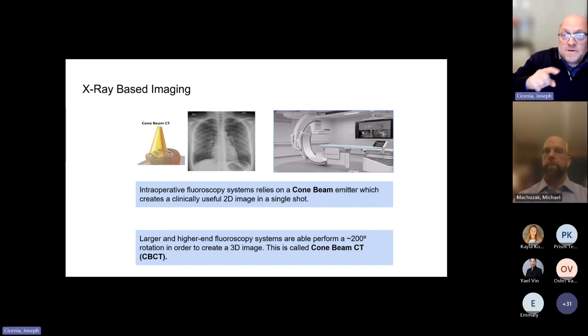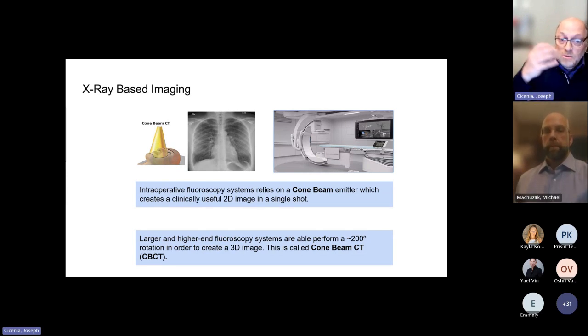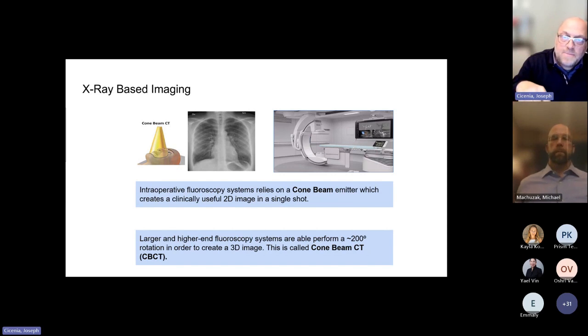If you spin that around and do images every degree or half a degree as you move around the gantry, around the patient, you get a series of images which can be put together via an algorithm to create a 3D image. Larger high-end fluoroscopy systems can do very wide spins, 180 to 200 degrees rotation, and create very detailed 3D images. This is what we all know as cone beam CT.